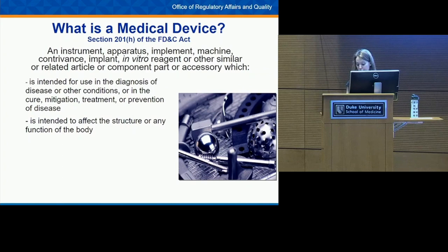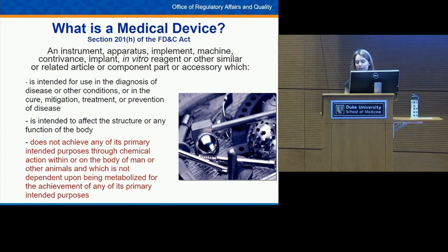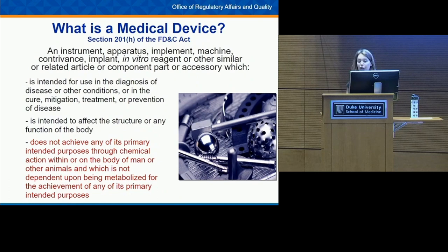Importantly, a medical device does not achieve any of its primary intended purposes through chemical action within or on the body of man or other animals, and is not dependent upon being metabolized. We like to think of medical devices as using physical or mechanical force — for example, a stent uses mechanical force to keep the artery open, not chemical action. Also, a device cannot use chemical action within or on the body, but it can use chemical action outside the body, such as a urine pregnancy test, which is still considered a medical device.